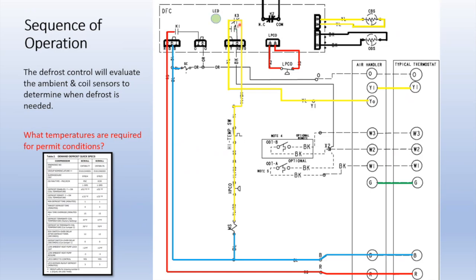So now that Y signal went through the K3 relay on the defrost board, came out here, goes through your high pressure cutout, and if you have a snap disc on your discharge line, through there as well. And now it's hitting the coil for your contactor that turns on your fan and your compressor.